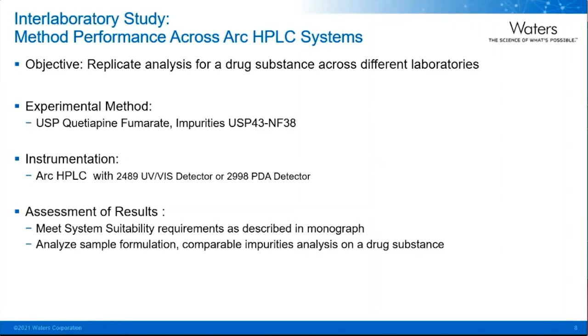We again use the same method as described earlier. However, this time our ARC HPLC system could have either a TUV 2489 detector or a photodiode array 2998 detector. This was because the availability of the detectors in the different laboratories varied. Again, we were going to assess our results by ensuring that we can meet our system suitability requirements as described in the monograph, as well as analyzing the sample formulation or drug substance and comparing the impurities analysis obtained.